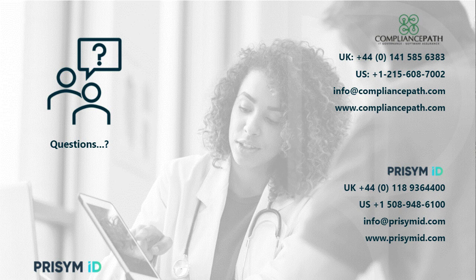But what has happened in parallel is that there was a move coming from the Case for Quality initiative in CDRH, which is the division of FDA that regulates medical devices, to provide guidance to industry on an appropriate approach for the validation, or what they're calling the assurance, of commercial off-the-shelf software.